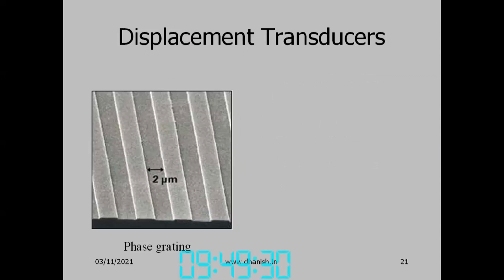Now we come to the most important part of the measurement system, that is the displacement transducer. So how do we make the measurement? That is through the displacement transducers. The most common type of displacement transducer is the transmission scale. It is basically a glass scale, through which light can be transmitted. On the scale are engraved lines like this in the photograph, with a certain width. A lot of lines are there. If you illuminate from one side, where it is engraved, it is opaque. Where it is not engraved, it will be transparent. So as the light moves, you can count the number of lines you have traversed, and that can be converted into a measurement. That is the basic way a transmission scale works.